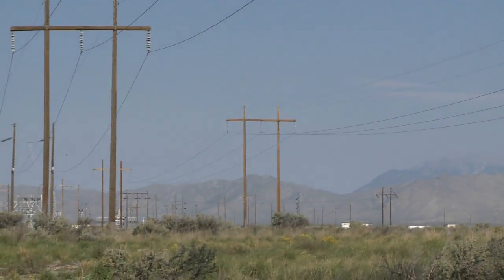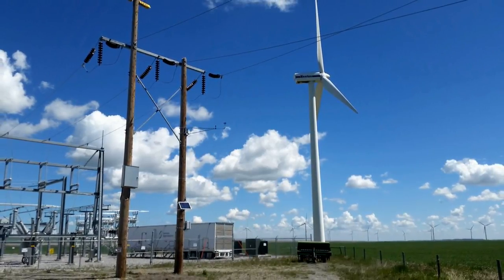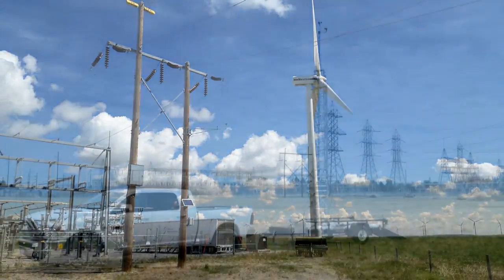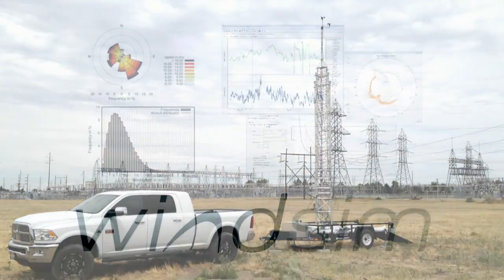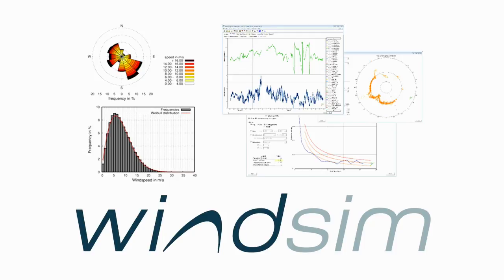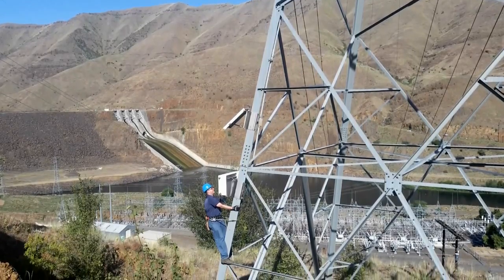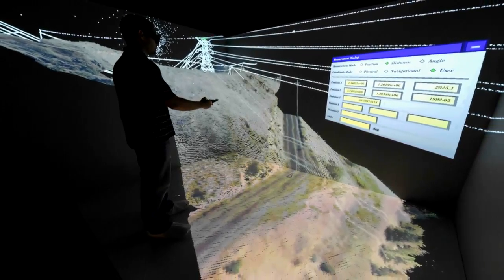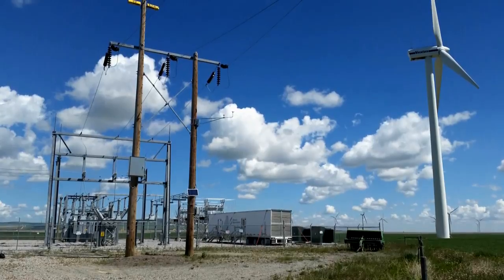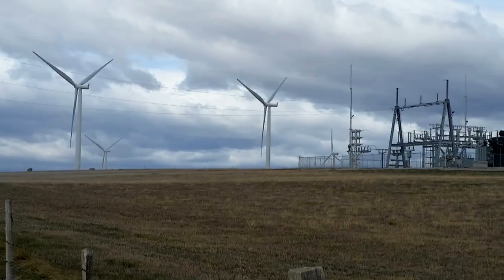Real-time information about line temperature has traditionally been difficult to obtain. INL's approach uses an optimized number of customized but commercially available weather stations placed in a limited number of carefully selected locations. By enhancing software pioneered by WindSim, INL has been able to incorporate data from dozens of weather stations into a single computational fluid dynamics model. Its resolution is fine enough to resolve wind speed and direction at each span as an end-to-end solution.